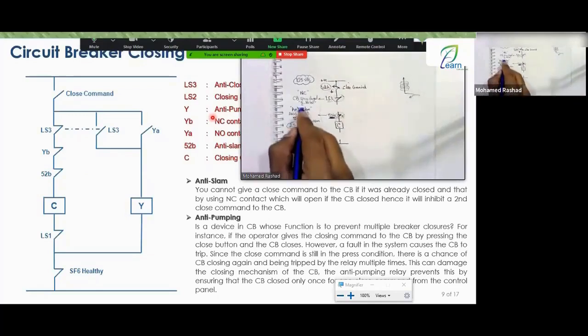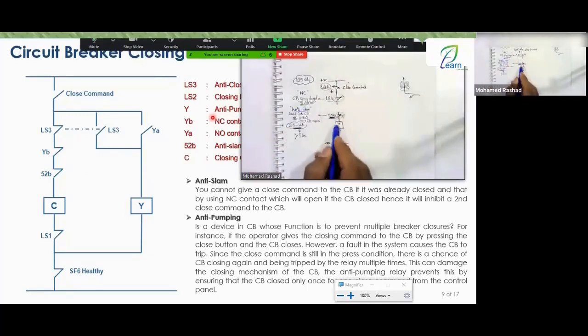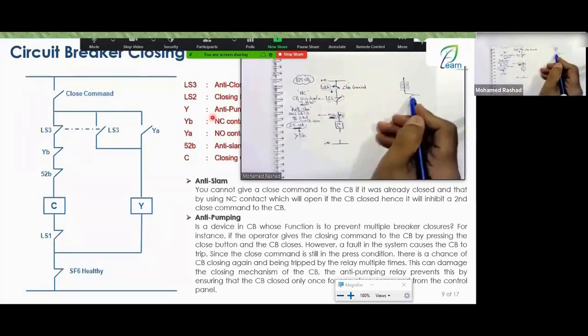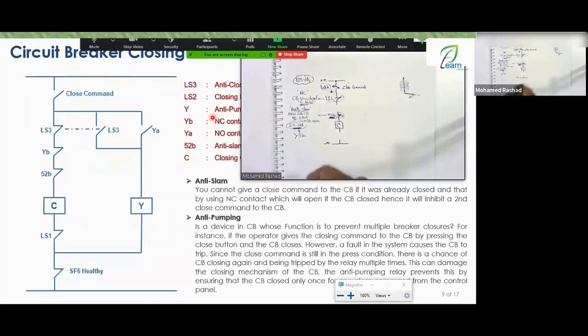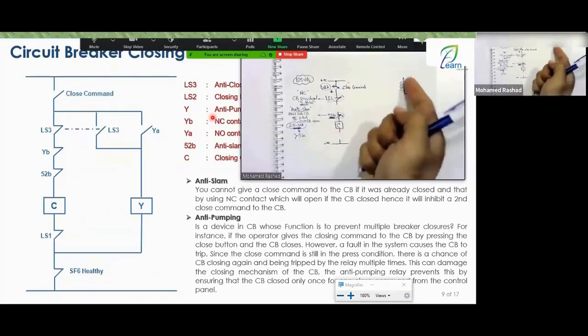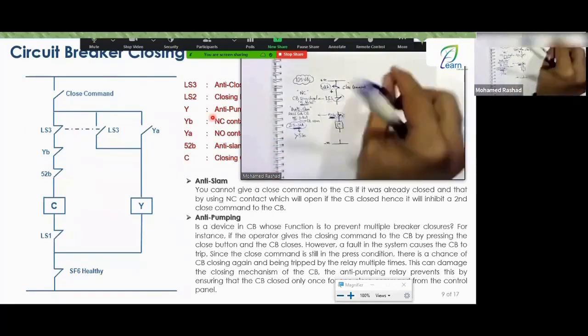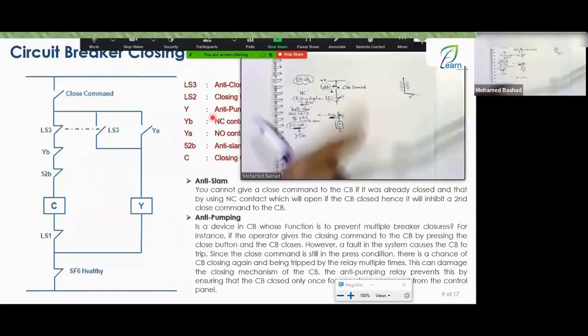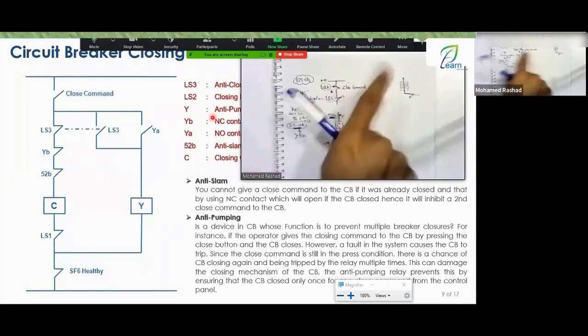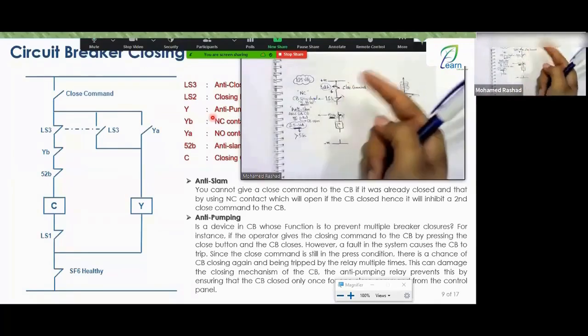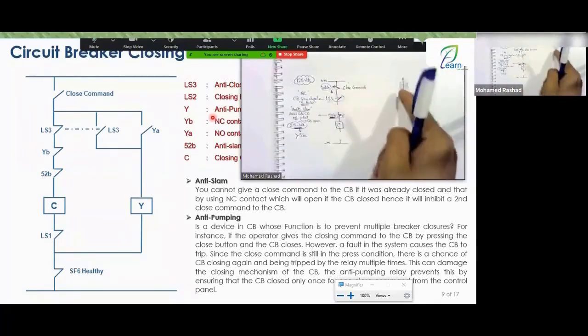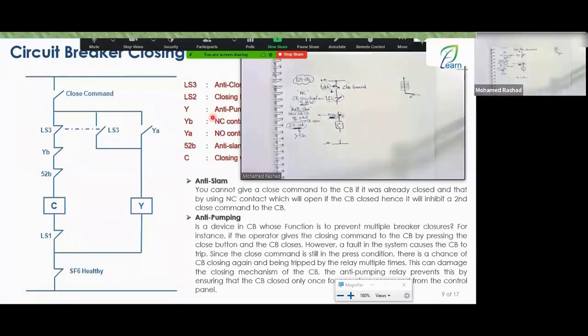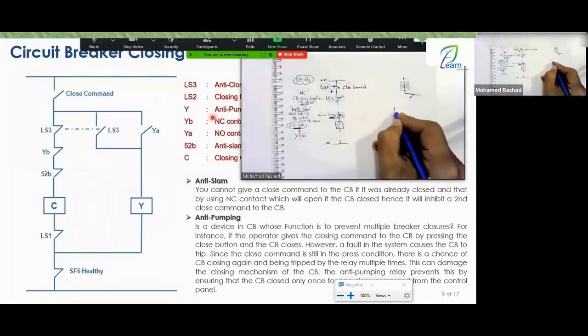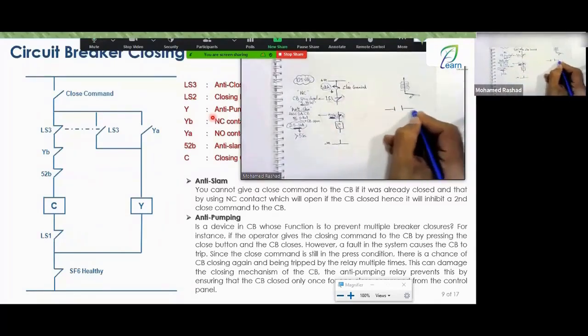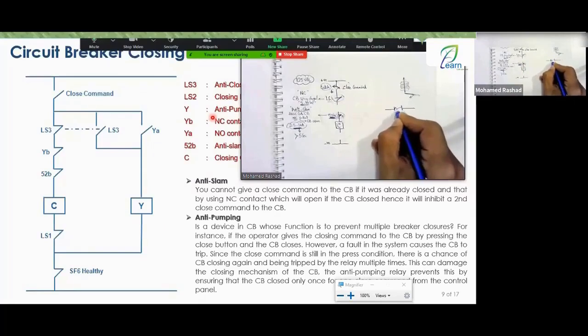So naturally, at close intervals of 5 to 10 seconds, you supply DC to the coil. The coil, of course, draws current to release its latch, and naturally, due to the passage of a 3 amp current through it, it will heat up slightly. Every 5 seconds, you keep supplying it with current, and with the frequent passage of current through it, it will burn out. That's one thing.